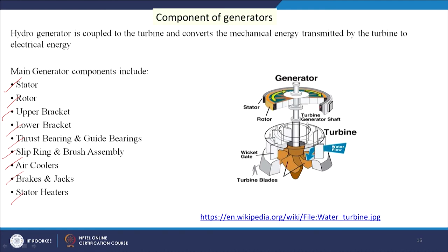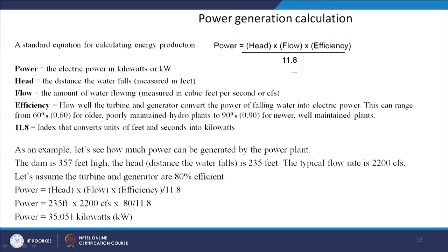Power generation in the FPS system is calculated as: Power (kW) = Head (feet) × Flow (CFS) × Efficiency / 11.8. Efficiency reflects how well the turbine and generator convert falling water into electric power, ranging from 60% for older poorly maintained plants to 90% for newer well-maintained ones. The factor 11.8 converts units of feet and seconds into kilowatts.